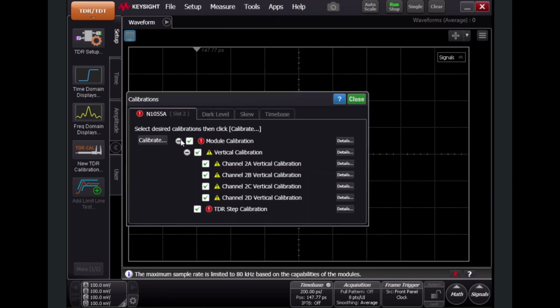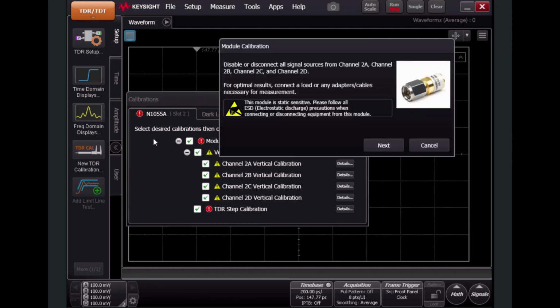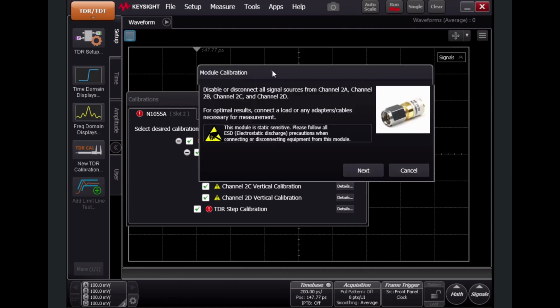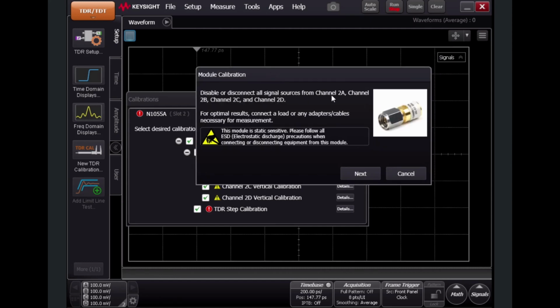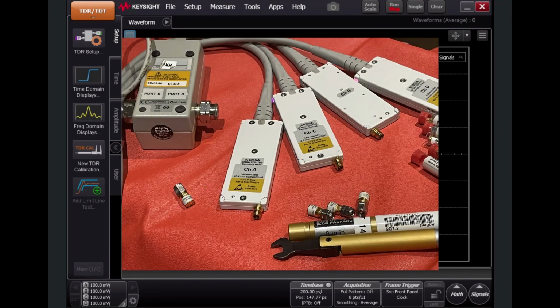It gives you a warning. We need to do a module calibration and vertical calibration, the TDR step calibration. So I'm going to do a full calibration, including the TDR step calibration. When we go to calibrate, we're walked through the calibration procedure, which is very easy to do. Say calibrate. Importantly, you must disable or disconnect any sources, and for optimal results, connect a load or any adapters necessary for the measurement. I'm not going to use a load in my measurement. For this initial module calibration, I'm going to remove everything.